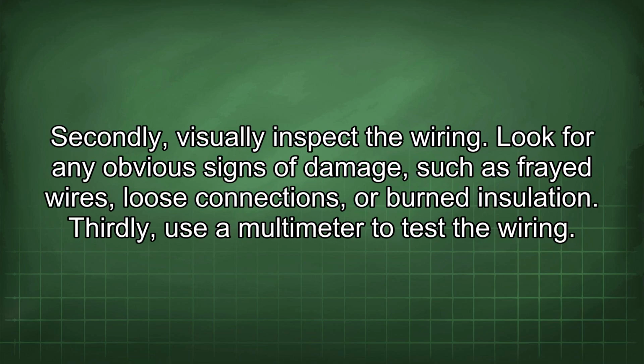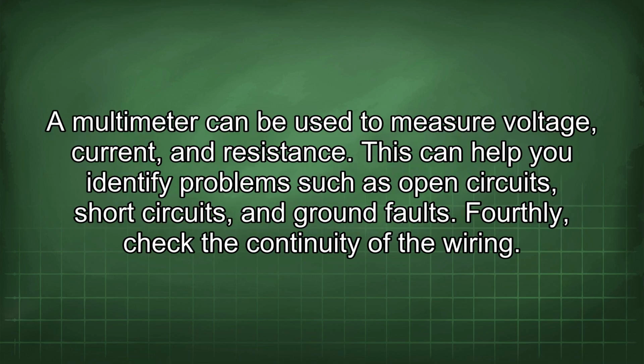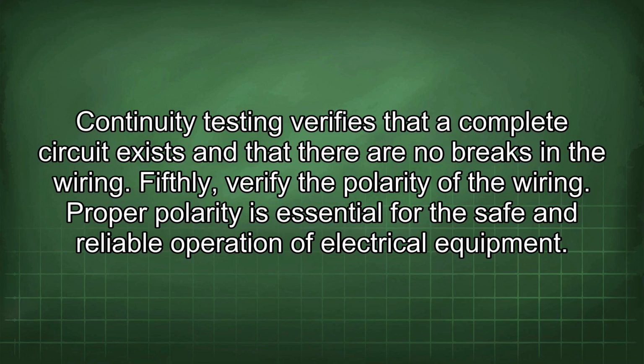Secondly, visually inspect the wiring. Look for any obvious signs of damage, such as frayed wires, loose connections, or burned insulation. Thirdly, use a multimeter to test the wiring. A multimeter can be used to measure voltage, current, and resistance. This can help you identify problems such as open circuits, short circuits, and ground faults. Fourthly, check the continuity of the wiring. Continuity testing verifies that a complete circuit exists and that there are no breaks in the wiring.